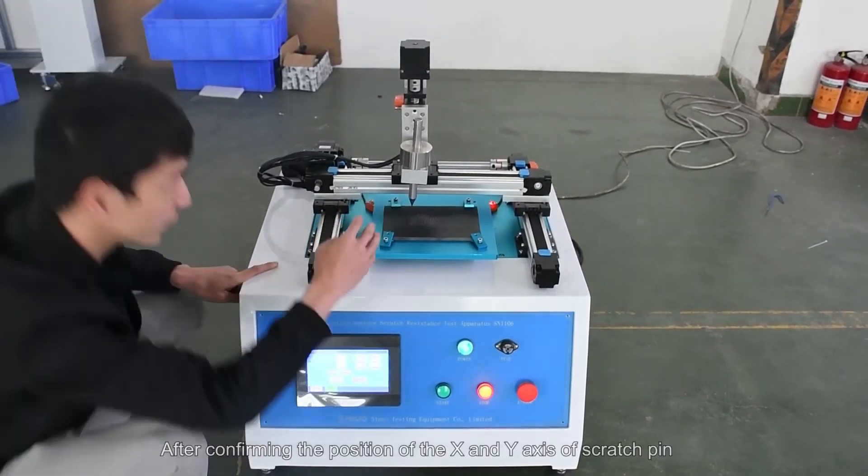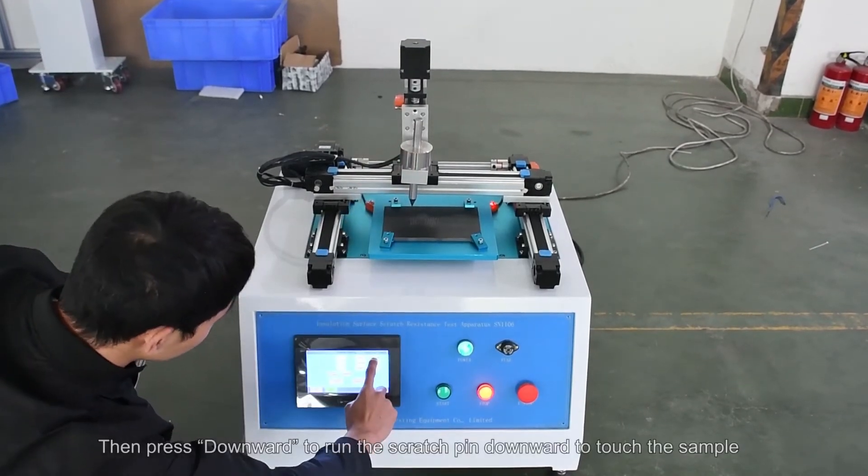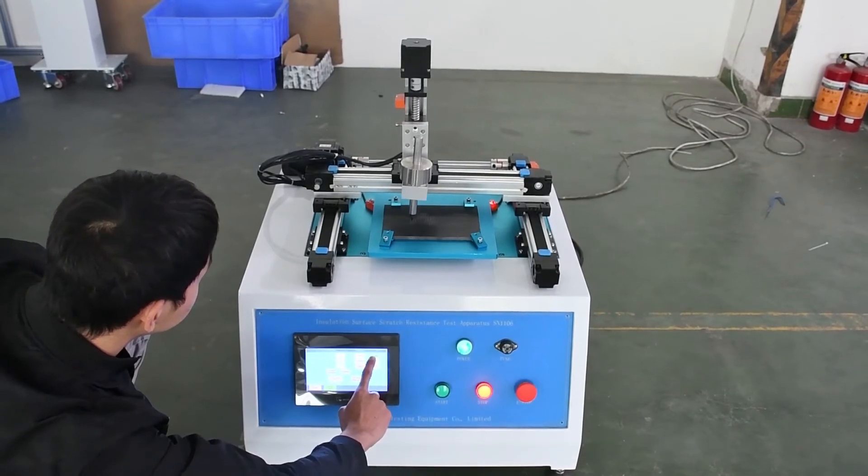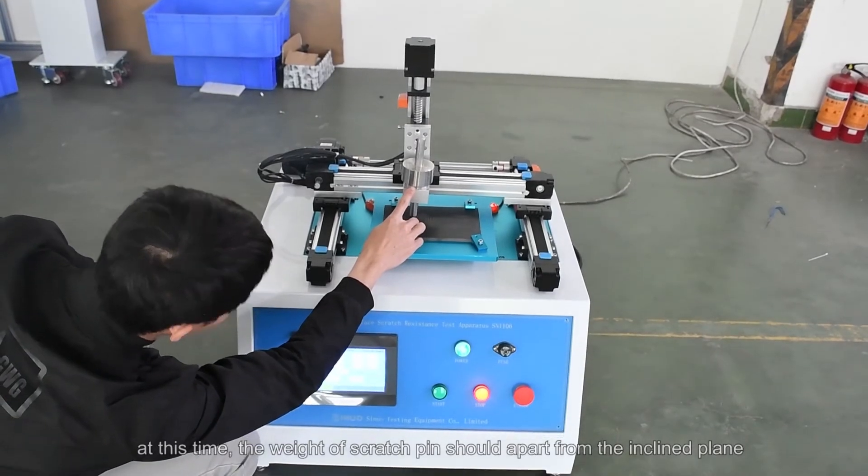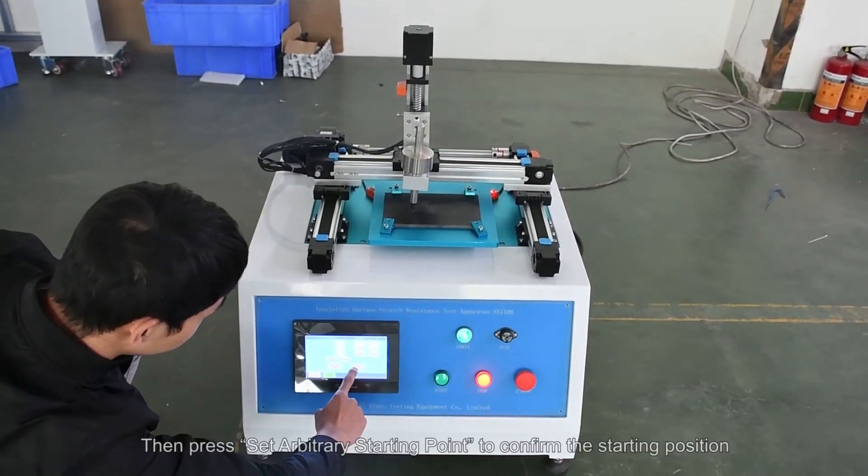After confirming the position of the X and Y axis of scratch pin, then press downward to run the scratch pin downward to touch the sample. At this time, the weight of scratch pin should be apart from the inclined plane. Then press set arbitrary starting point to confirm the starting position.